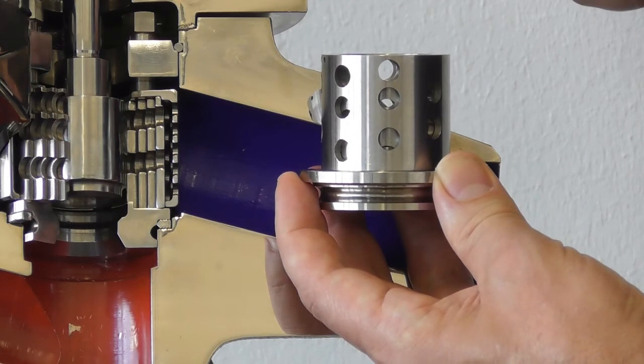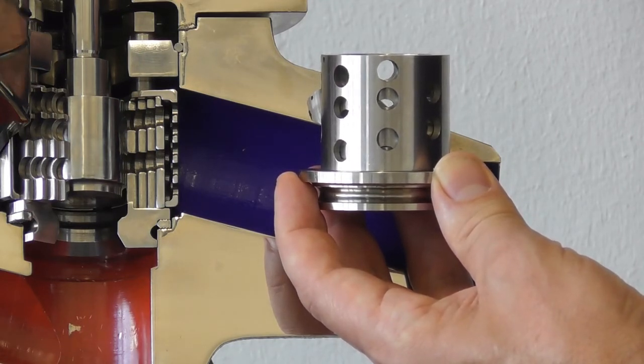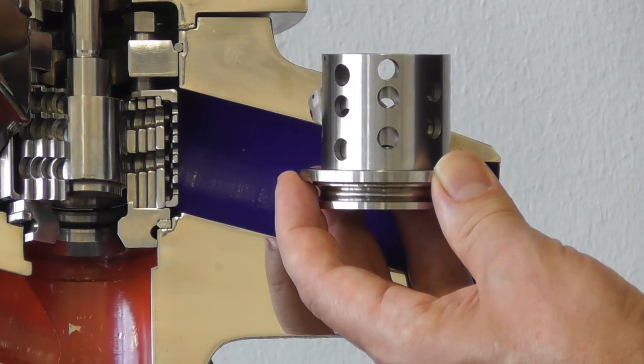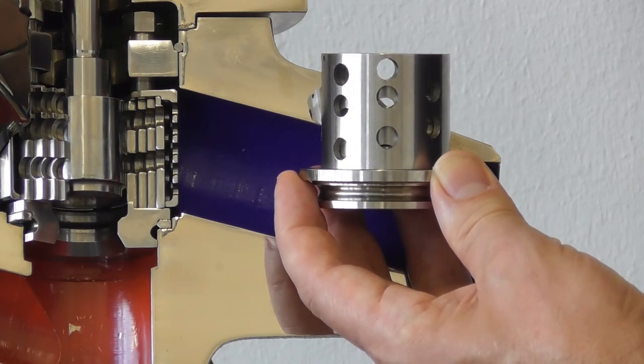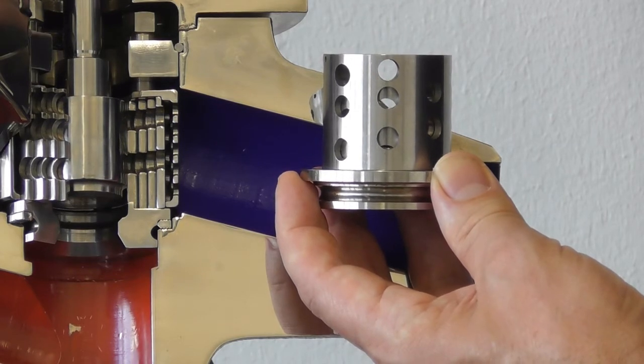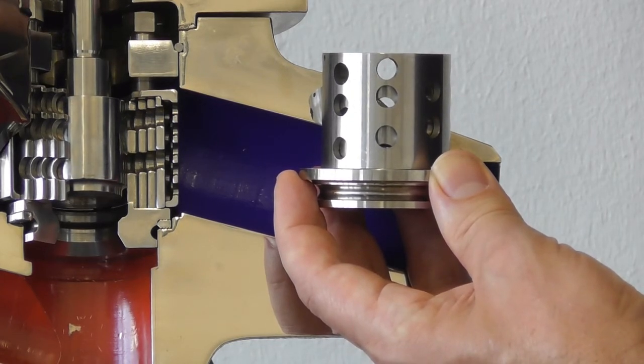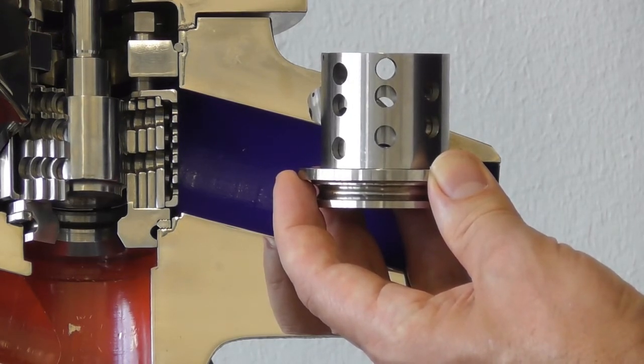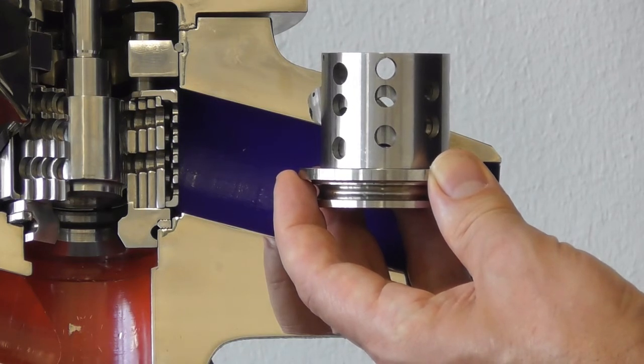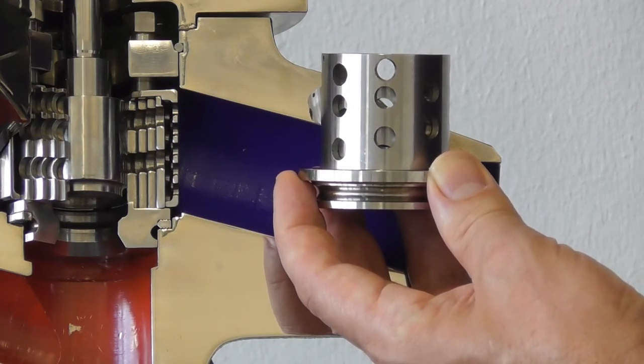Additionally, we have a special valve plug design and seat design, which guarantee zero leakage. That means we fulfill ANSI class 6 with a control valve, which has the function of two valves, the control valve plus an isolation valve.